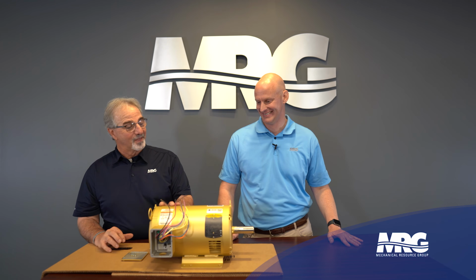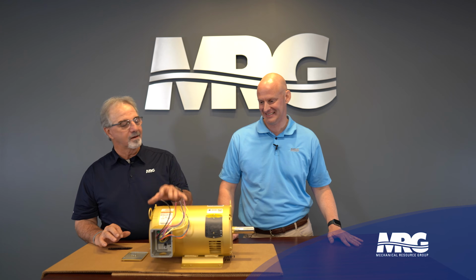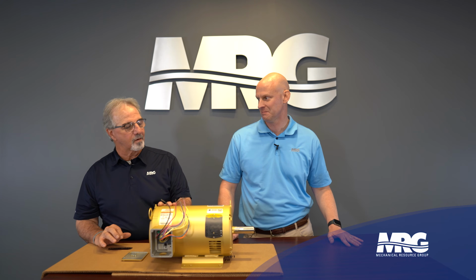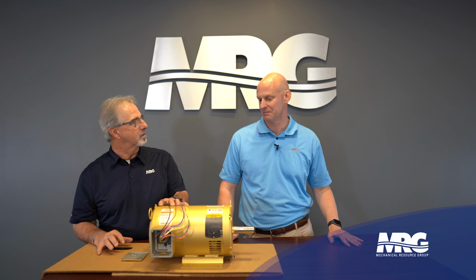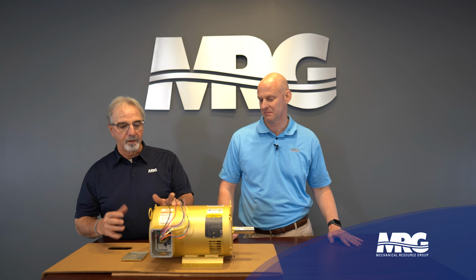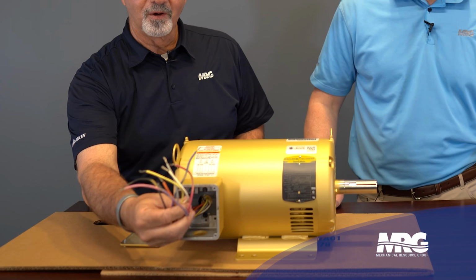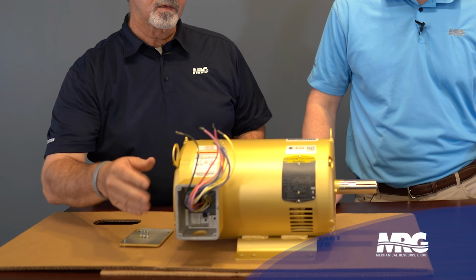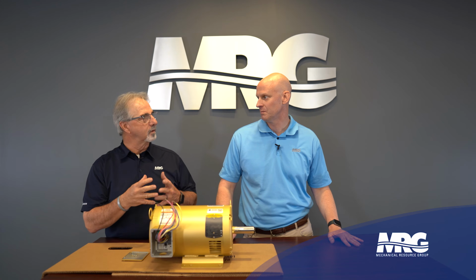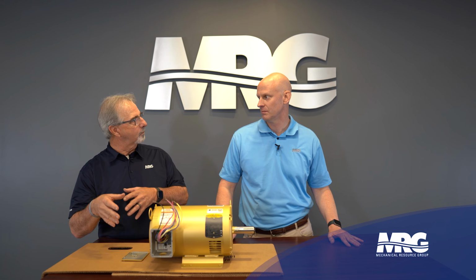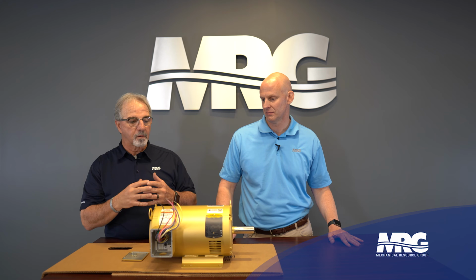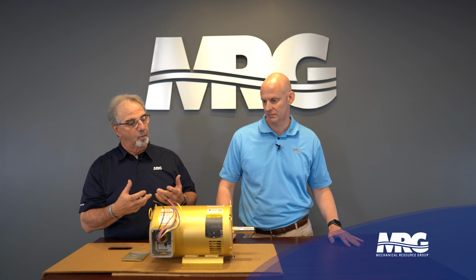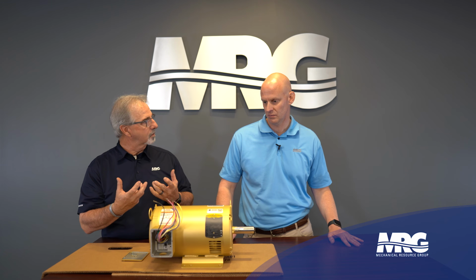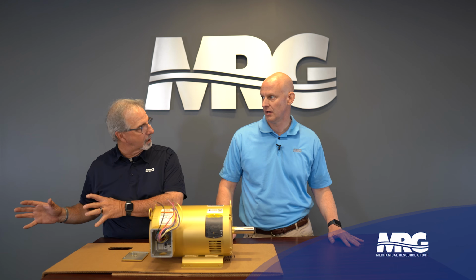Exactly. So, like I said, this motor here is what most air handlers, cooling towers, standard applications are going to see. It's going to be a 9-lead motor, and this is called the terminal block. This particular motor is dual voltage. It's suitable for 208, 230, or 460 volt connection. And when we pull in our connection diagram pretty soon, we'll walk through that. But I want to go through what you need to look for when you walk up to a motor so you have a good idea of what you're dealing with and know your starting method.